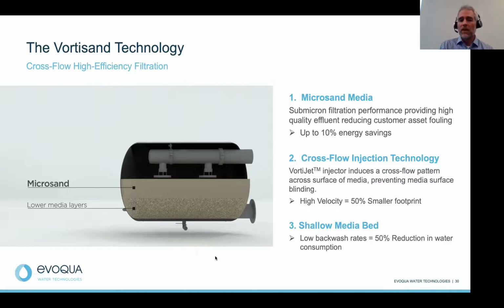So water is ultimately injected into the top of the manifold, and it basically flows vertically down into an injector. We utilize a very unique, actually patented, cross-flow technology, with an injector called the VortiJet injector, which takes that vertical flow and induces a cross-flow pattern that creates a tangential flow across the surface of the media, really scouring the top of the layer and preventing any surface blinding. Now that's very important because if you utilize such a very fine media, you wouldn't be able to achieve such high velocities.